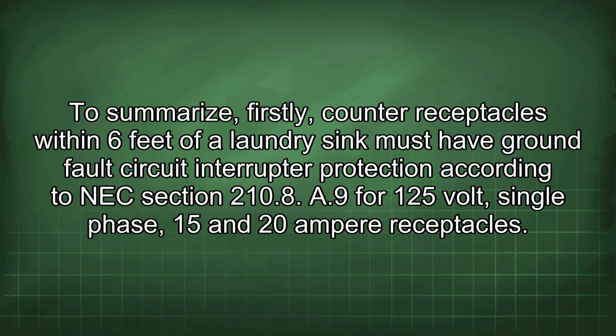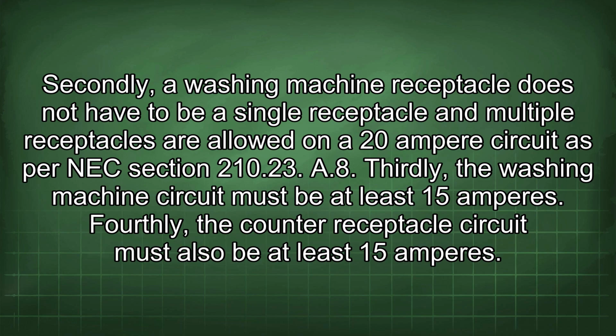To summarize, firstly, counter receptacles within 6 feet of a laundry sink must have ground fault circuit interrupter protection according to NEC Section 210.8(A)(9) for 125-volt, single-phase, 15 and 20 ampere receptacles. Secondly, a washing machine receptacle does not have to be a single receptacle, and multiple receptacles are allowed on a 20 ampere circuit as per NEC Section 210.23(A)(8).